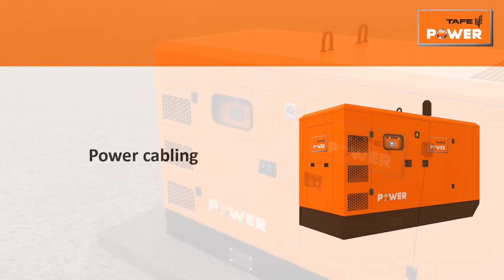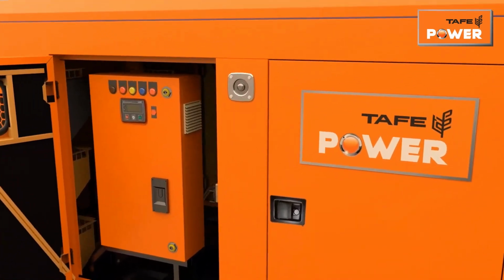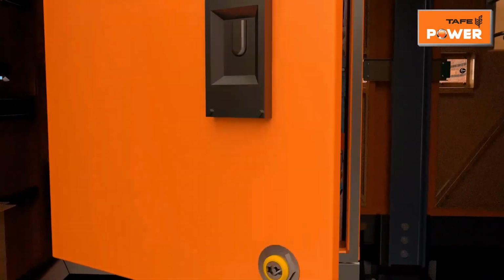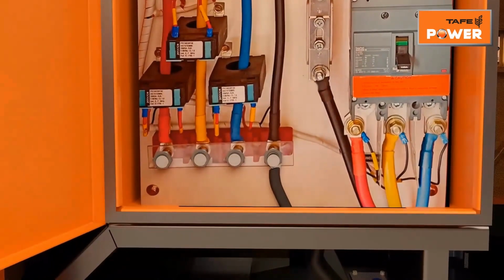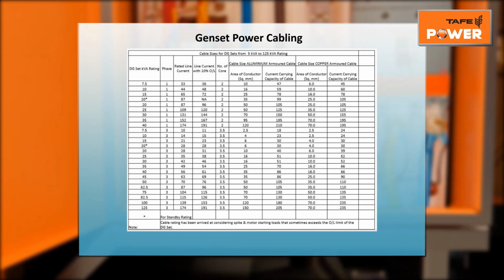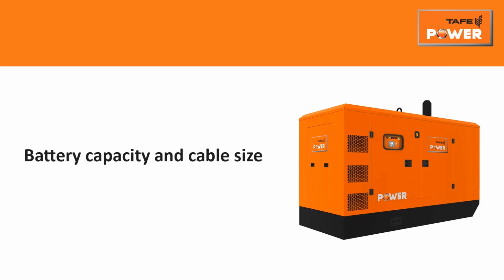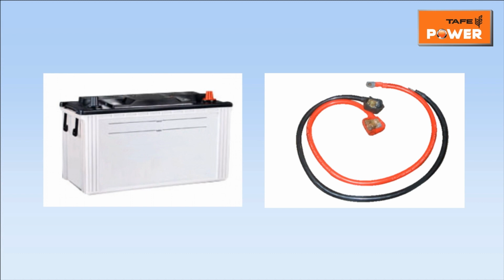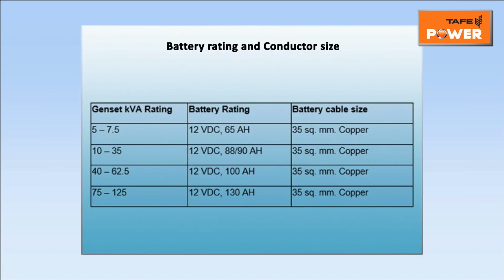Power cabling. Connect power cable of recommended size using proper gland and lugs. Ensure proper crimping of lugs with cable and firm tightness of power cable nuts at terminals. Battery capacity and cable size. Use recommended size battery cable with proper lugs and terminal connector. Use recommended capacity of battery as per genset rating.